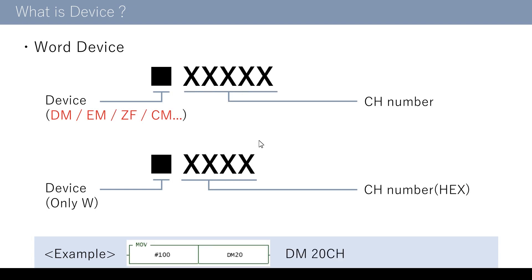In the case of the word device, the numeral value indicates the channel number directly. There are the following device names: DM is the one in which the unit function is allocated; EM and ZF store data in the program; and the PLC system data is allocated in CM. DM20 is the 20th channel of DM. However, for the device called W, used for Ethernet IP communications, all numbers indicating the channel number are hex numbers, such as WFF.